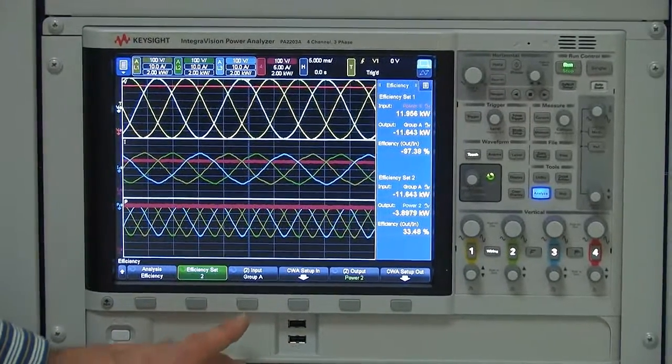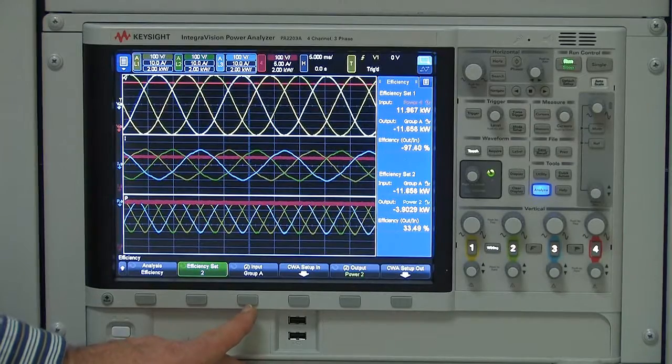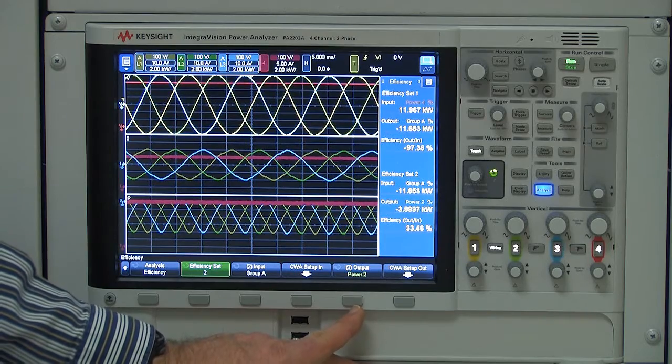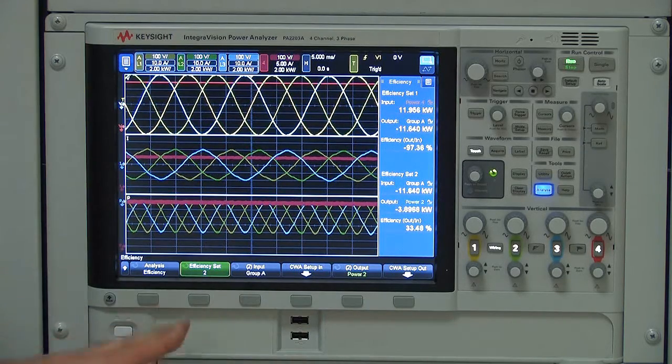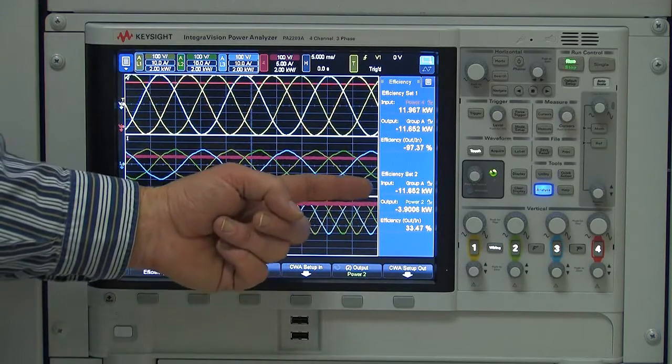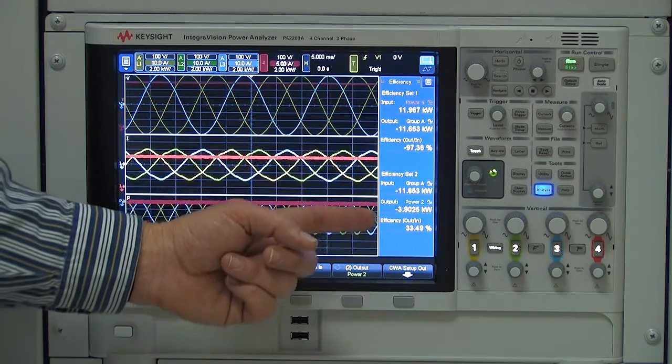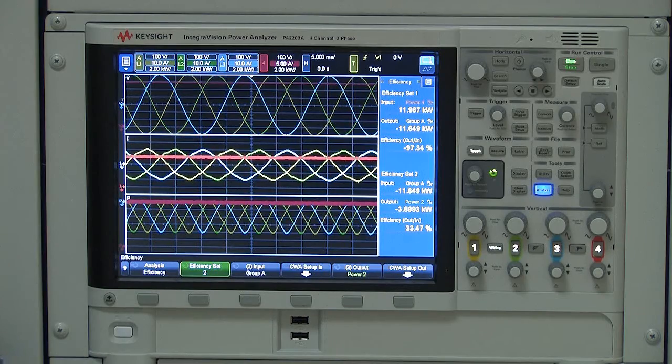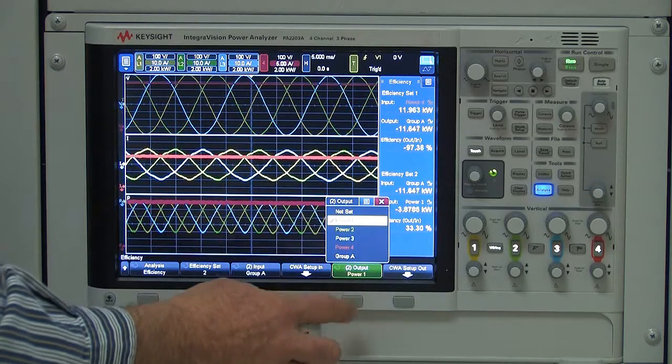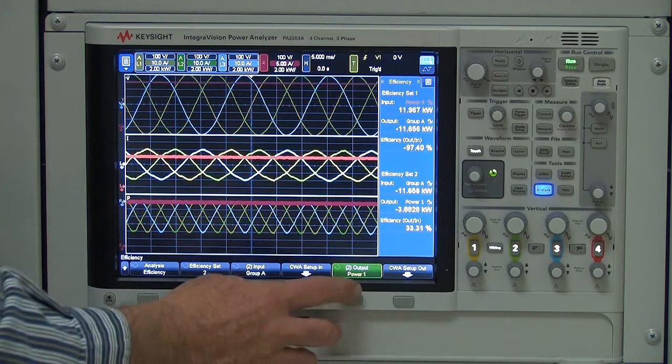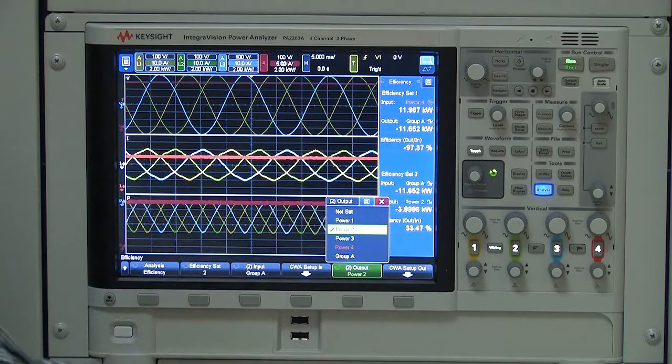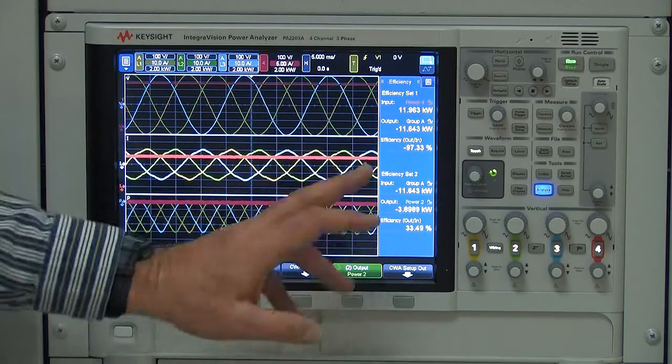In this case, I'm looking at the input being the group A total power and the output being one of the phases of the power. So we'll see how well the power is being converted on a phase-by-phase basis. And if you look at this case, minus 11.6, minus 3.9 for an efficiency of 33.45. So you can see it's being split fairly equally between the three phases. You can look at each of the phases if you'd like by scrolling through them. And again, just about exactly 33% on each one of those.